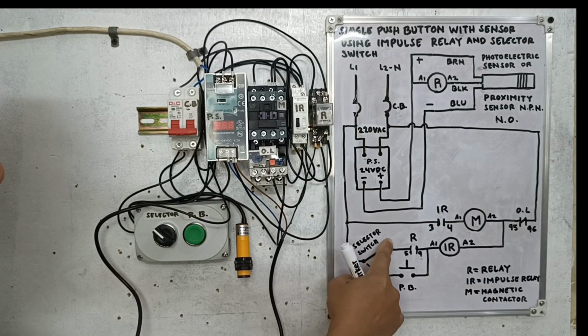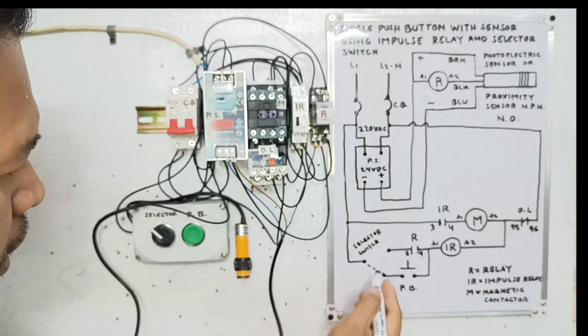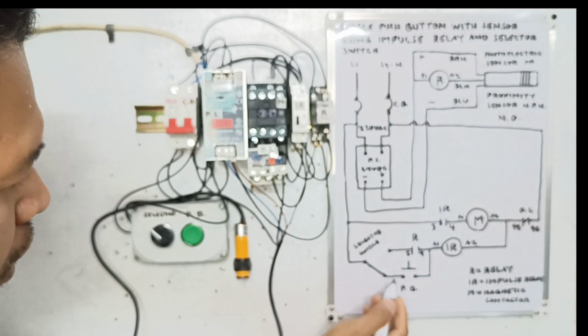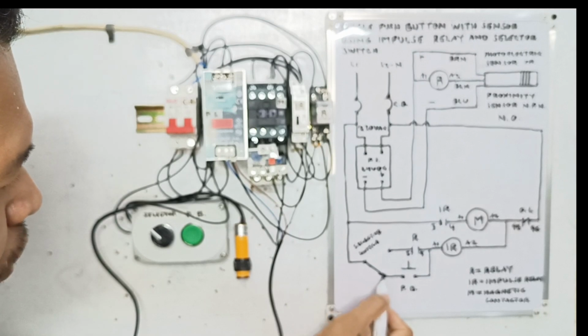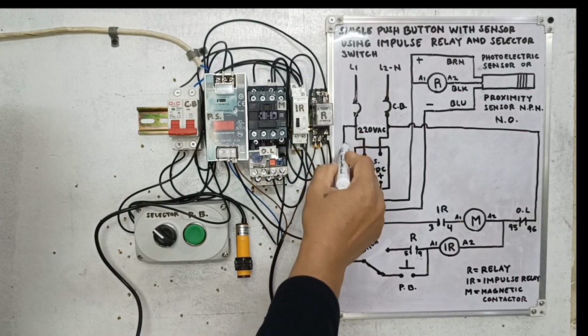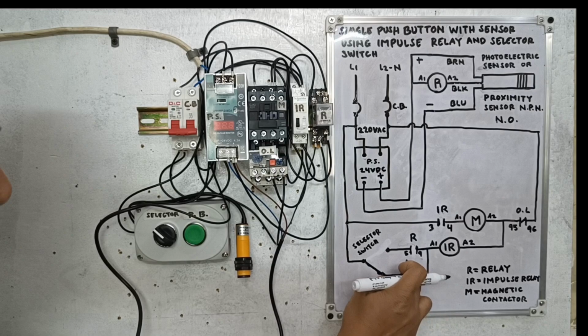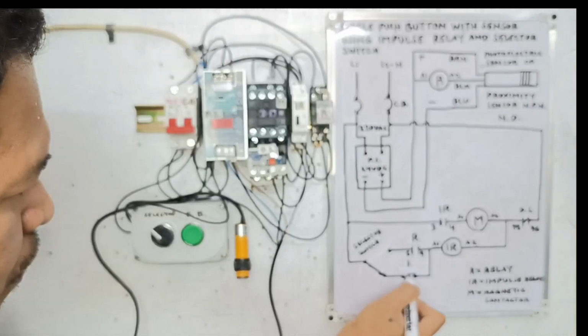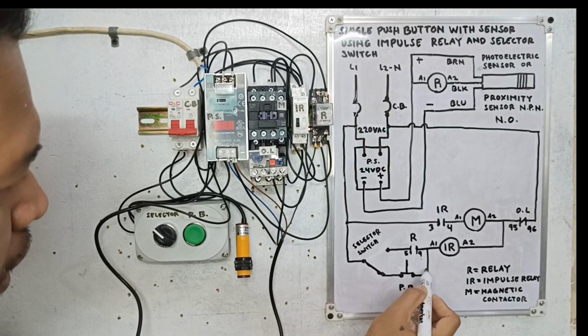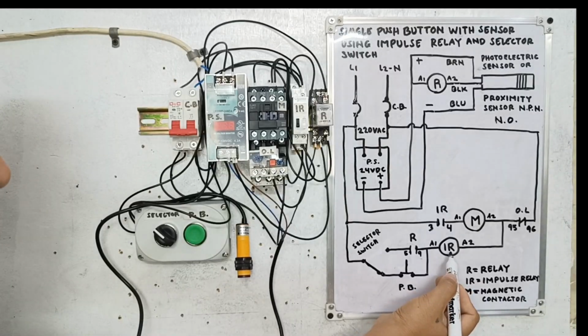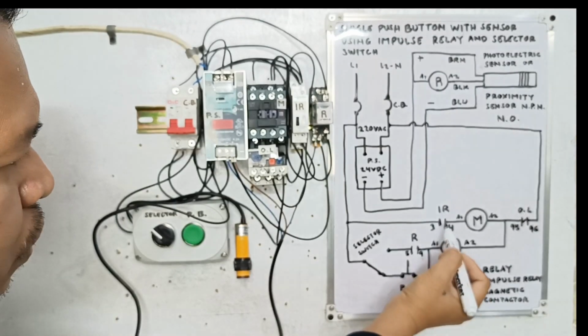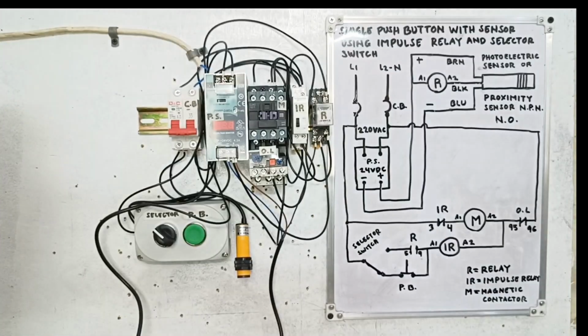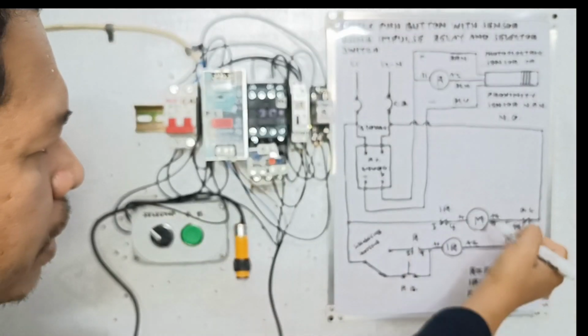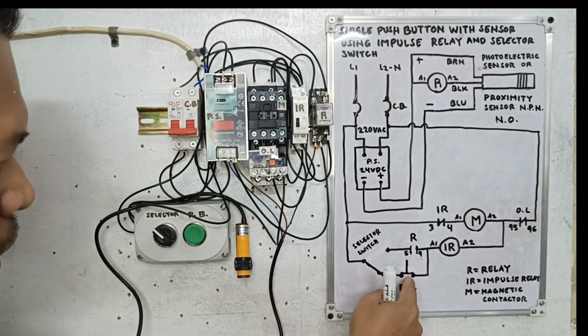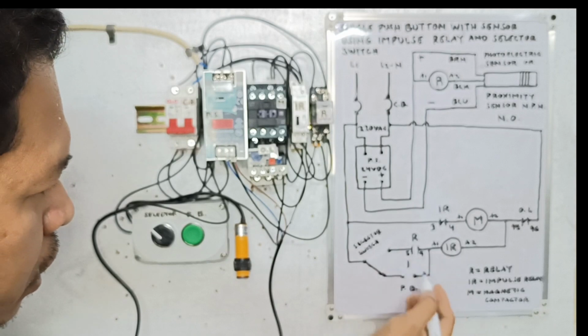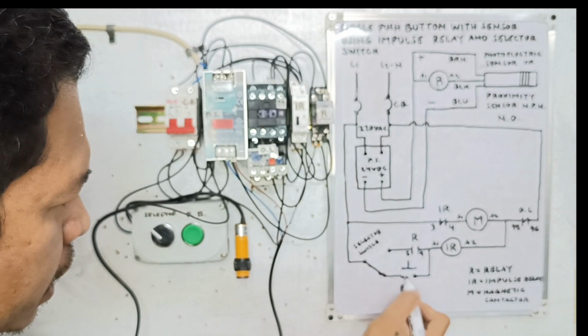Now, if the selector switch, we can put it on the other side, just like this, because our selector switch is single pole, double throw. If the selector switch selects that one, the current now passes through the push button. If you press this push button, guys, this one will close, the current passes here, and the impulse relay activates. After the impulse relay activates, this one will close, the normally open contact of the impulse relay. Now the current passes here and the magnetic contactor activates. After you release this button, guys, it will go back to the normal position, normally open, just like that.